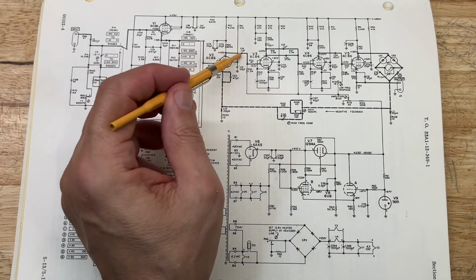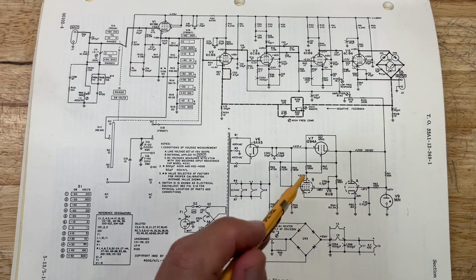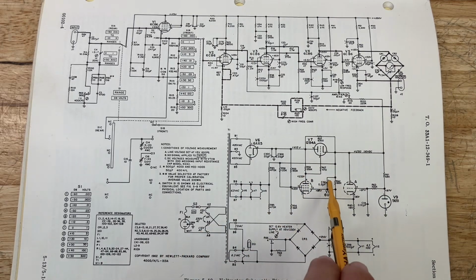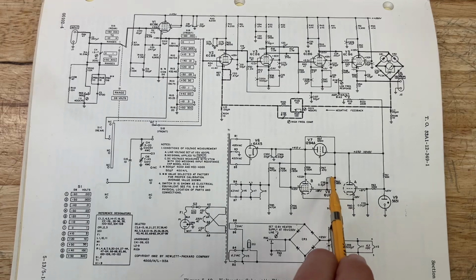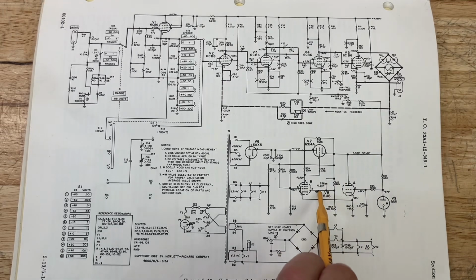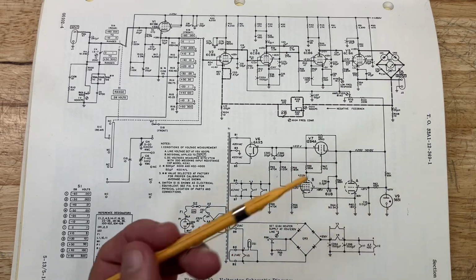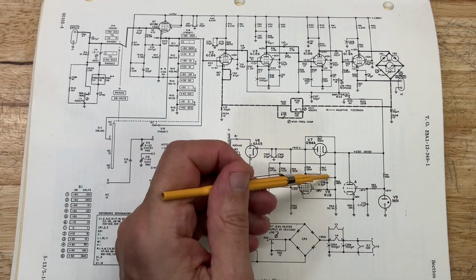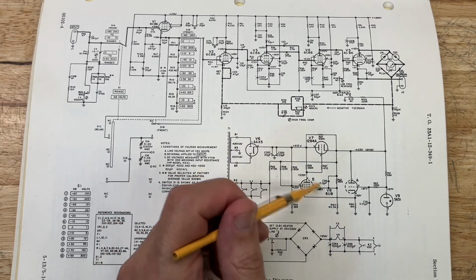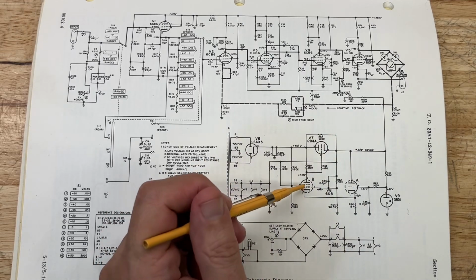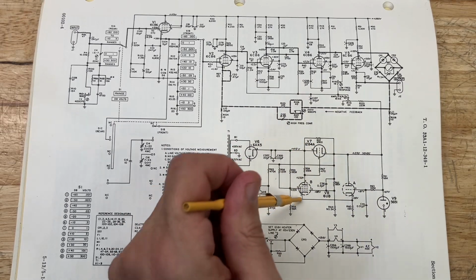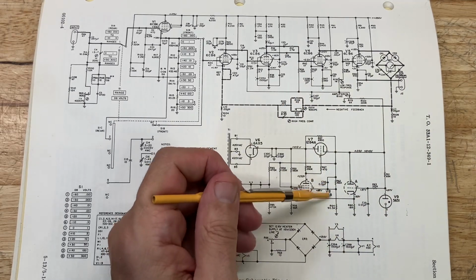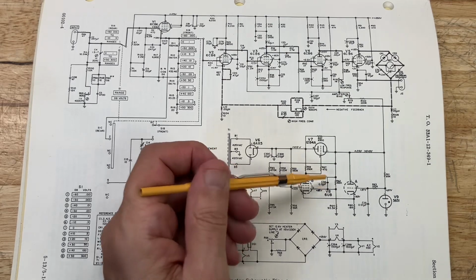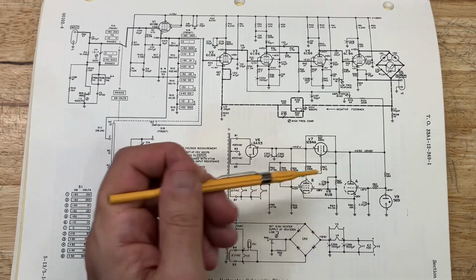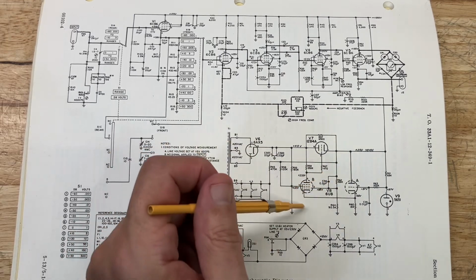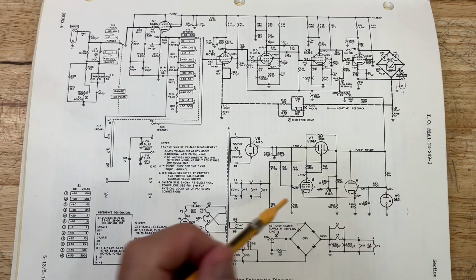There is a fourth one of those Black Beauty style paper capacitors. It turns out that it is over here in the power supply regulator circuit. This is not so critical. If it develops a small amount of leakage, it's not going to cause a catastrophic failure of the instrument. So I'm not too worried about replacing that one over here. It's just used in the startup of the regulator circuit of the high voltage supply. Once this capacitor charges to its full voltage, it effectively is disconnected from the circuit and no longer has any function in the circuit. It's only used at power up.